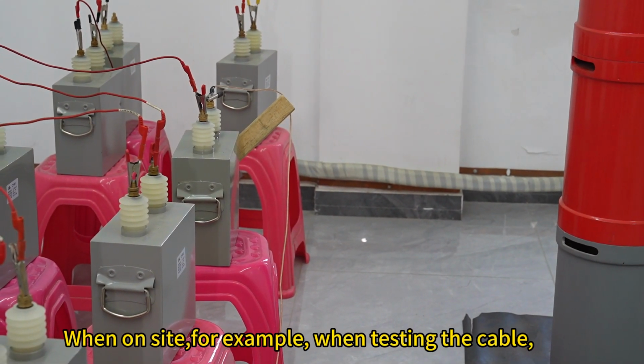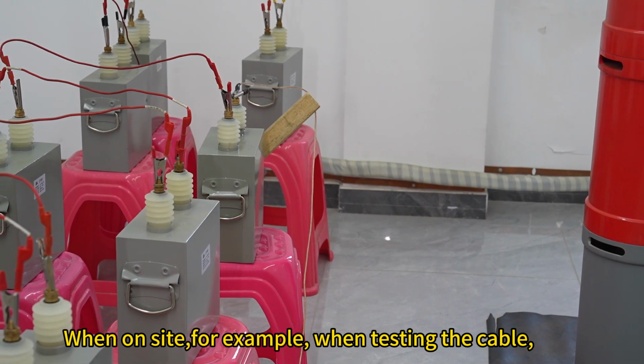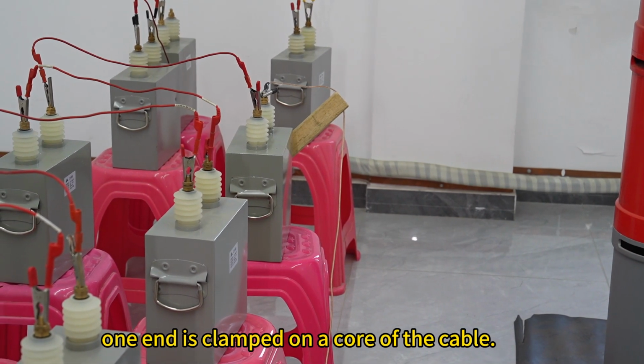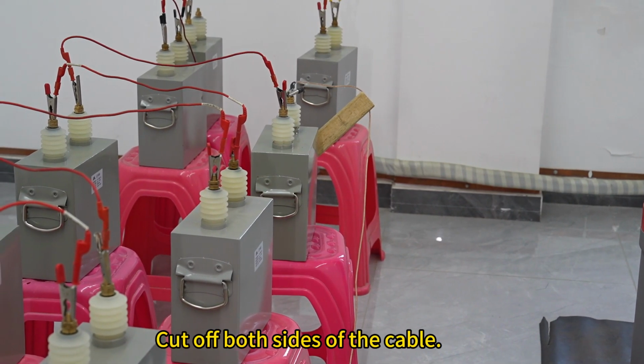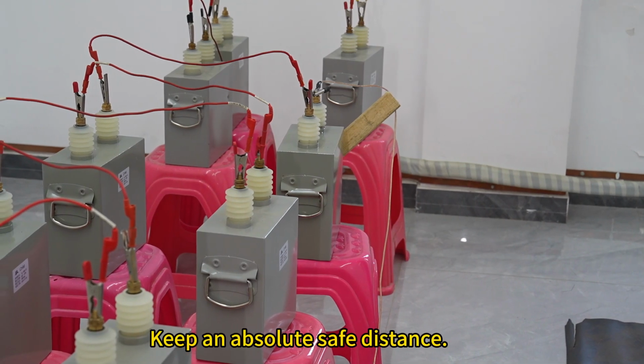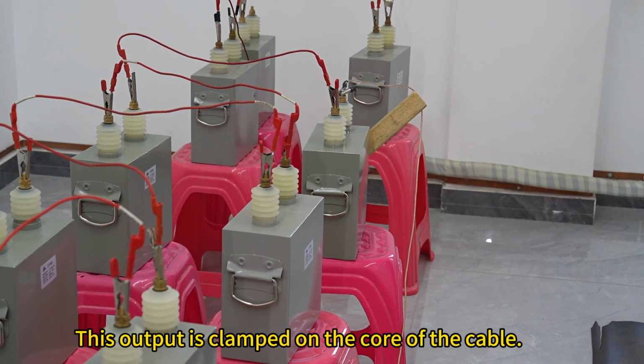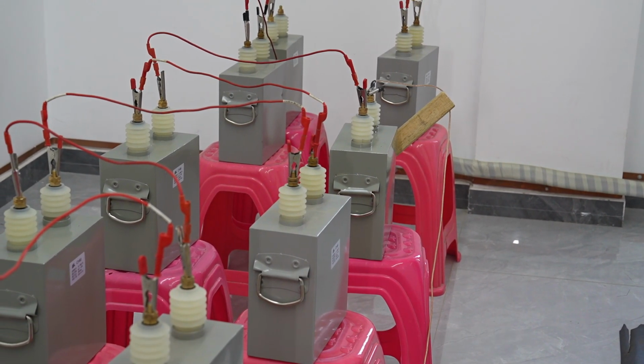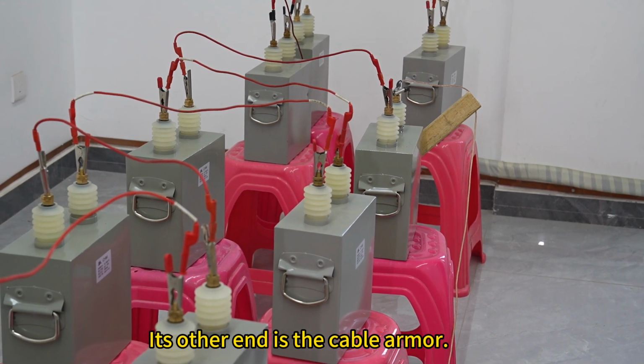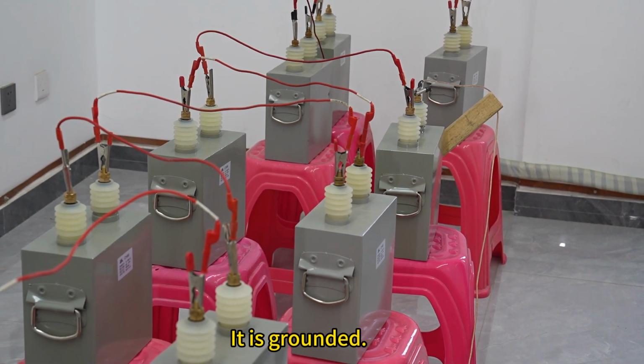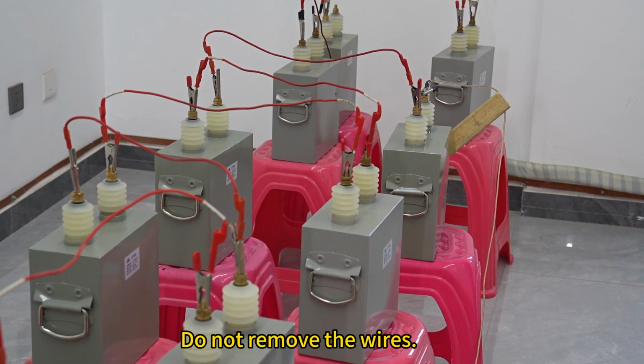When on site, for example, when testing the cable, one end is clamped on a core of the cable. Cut off both sides of the cable. Keep an absolute safe distance. This output is clamped on the core of the cable. Its other end is the cable armor. It is grounded. Do not remove the wires.